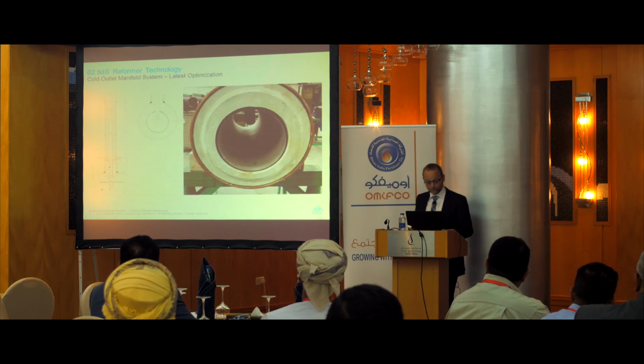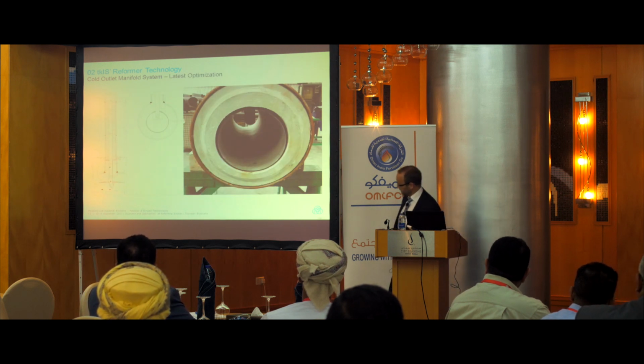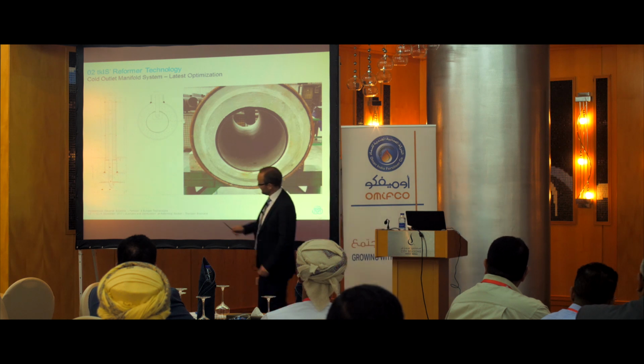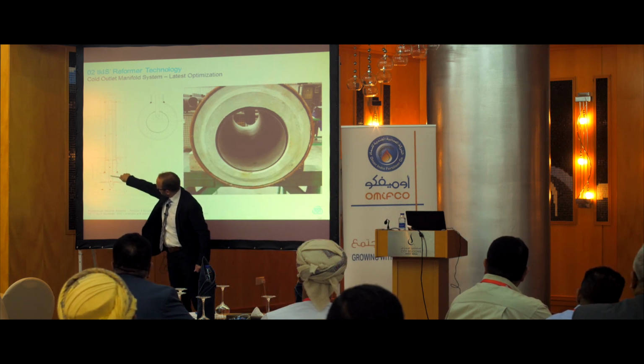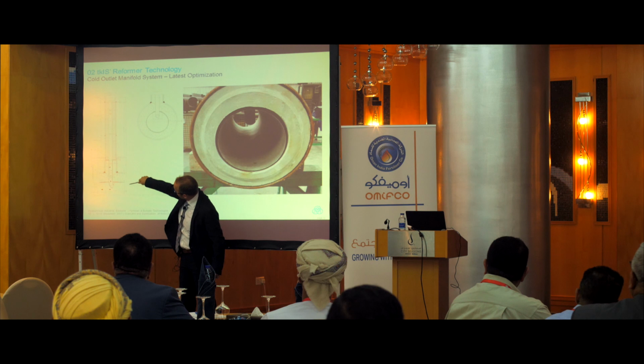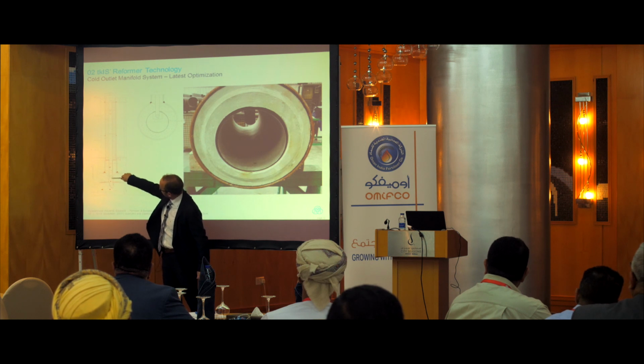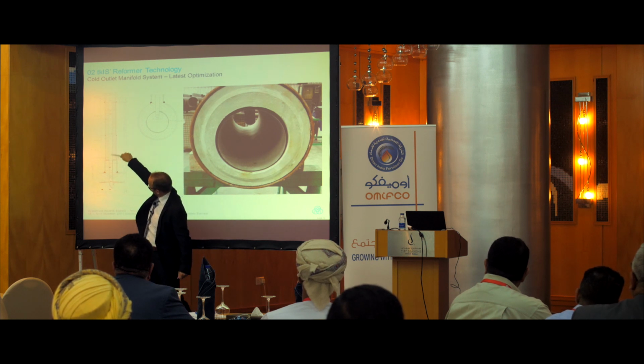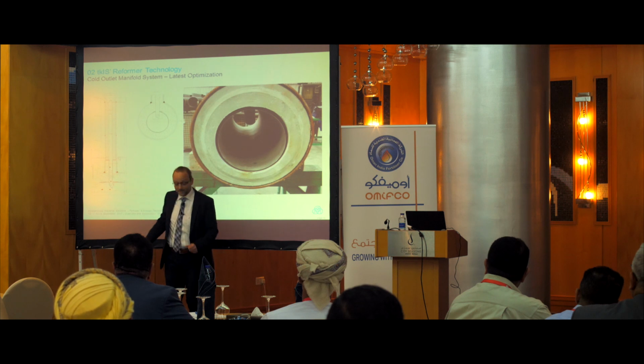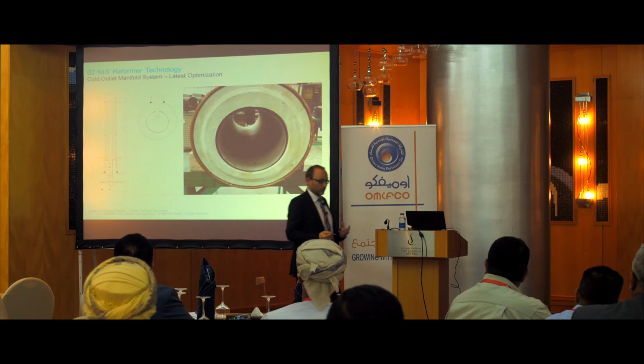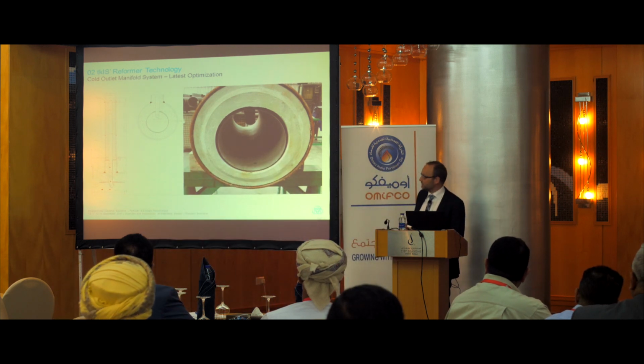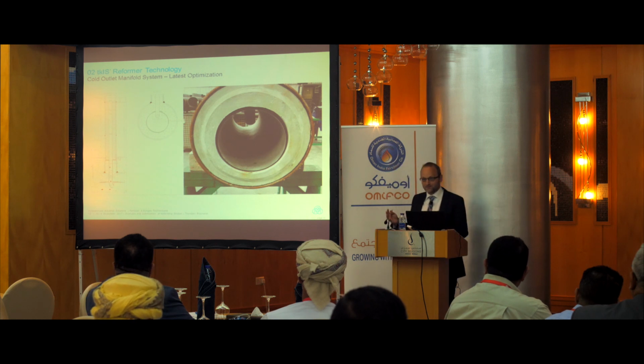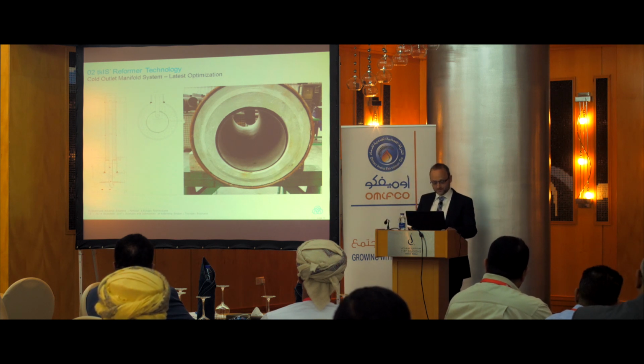Also here, of course, we have improvements over time. The latest improvement is a curved inlet band. That is a connection to the reformer tube, and this curved band shall reduce any pressure drop at that location, and shall also reduce any drift for any bypasses within the system.